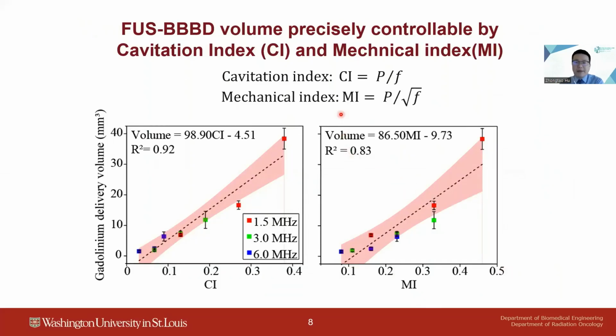Cavitation index and mechanical index were proposed before as indicators to predict the FUS BBBD drug delivery outcome. Cavitation index is defined as pressure over frequency, and the mechanical index is defined as the pressure over the square root of the frequency. We can find the gadolinium volume has a strong linear correlation with the CI and MI, and the correlation coefficient of CI is slightly higher than that of MI. Those findings are important as they indicate our FUS device can precisely control FUS BBBD outcome.